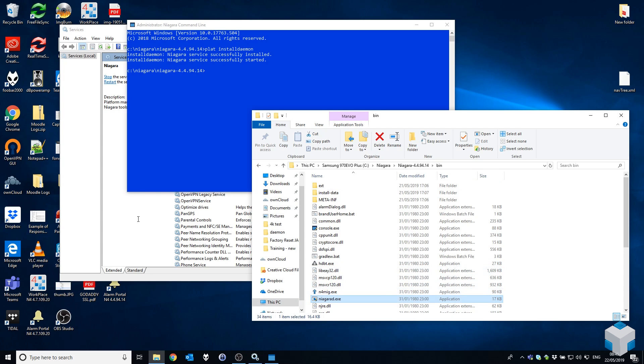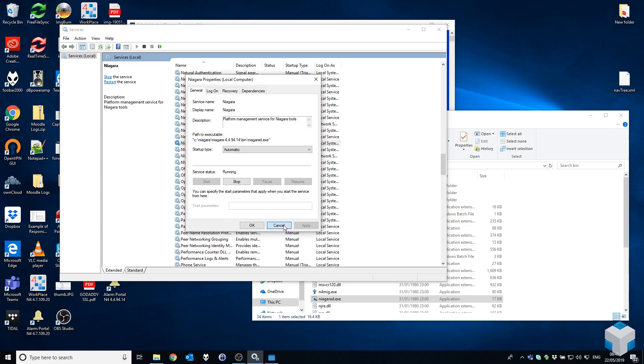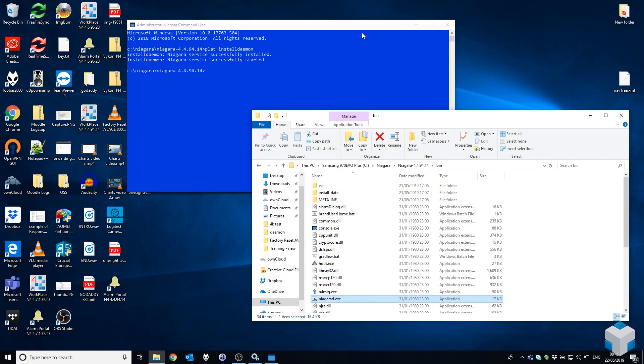So what that means is if we now go into our Windows services and refresh the view, you will see the Niagara service path to executable now points to 4.4.94.14. This means our platform daemon is running in the same version as workbench, which we are about to launch. That means you're effectively running a completely clean and separated 4.4 platform daemon and 4.4 workbench.